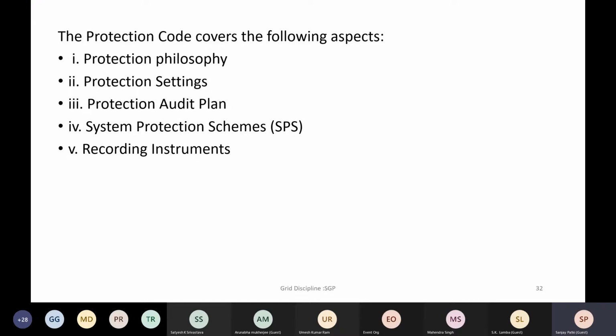This is the provision related to the protection code in the grid code, in terms of protection philosophy, protection settings, protection audit, and special system protection schemes, the recording instruments. These were all recommended as part of the recommendations after the 2012 grid collapse, and subsequently incorporated in the grid code. Reference is also made for the protection philosophy and protection setting to the CBIP manual on protection, which is taken as a reference manual. It is mentioned in the regulation and grid code. These guidelines should be followed.